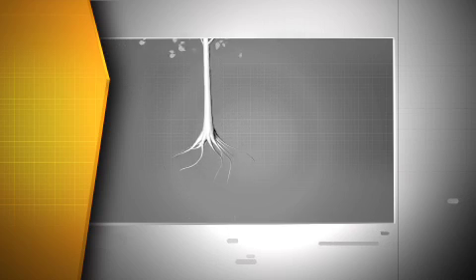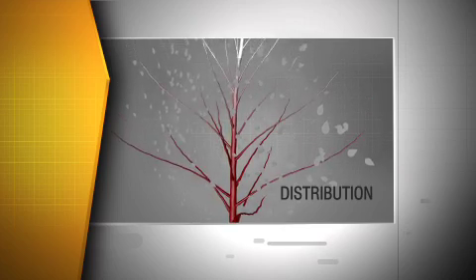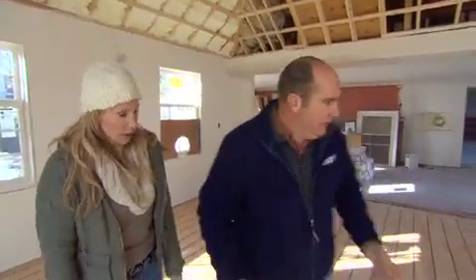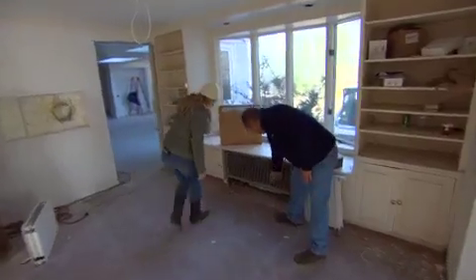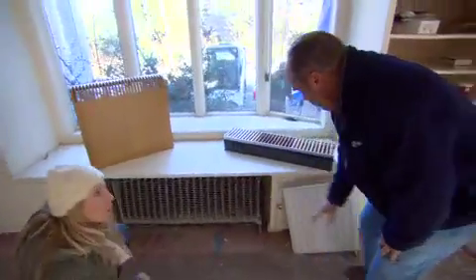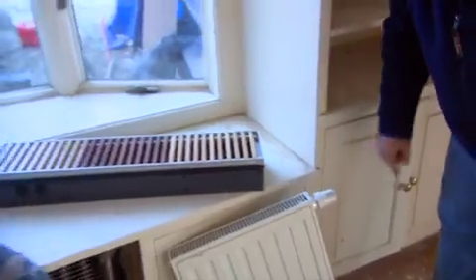You're really talking about heating the person and the body and not wasting energy heating all the space around you. There really is no better way to heat the human body than radiant heat. A hydronic system is like a tree — its roots are the basic boiler or heat source, the trunk gets the water through the building, and the leaves are the heat emitters. Radiant is just one of these heat emitters. We've got a bunch of choices. This house originally had cast iron convectors sitting underneath this cabinet. They draw air in from the bottom, heat it up, and it comes out through the top. We're going to take these existing convectors and add a thermostatic radiator valve that'll sense the temperature at every single radiator. The original way this house was heated was the most efficient way, but what we're doing is customizing it so it can actually be a controlled environment.